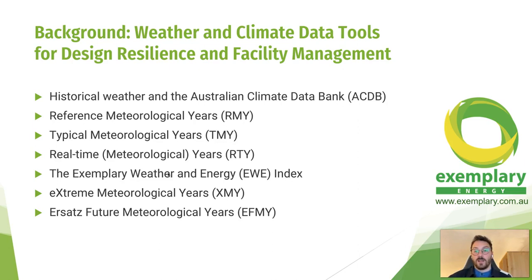This weather and climate data is used a lot throughout the industry by developers, both for residential and commercial buildings of all types. For example, someone might be familiar with Section J of the National Construction Code, where for demonstrating compliance, you can develop a computer model of the building, and then you apply the relevant local climate data to evaluate the performance. And then what you do is compare the model to another model that was built using the deemed to satisfy energy provisions in the NCC. And if you can demonstrate that your building is more efficient than the deemed to satisfy building, then your design can be deemed to comply.